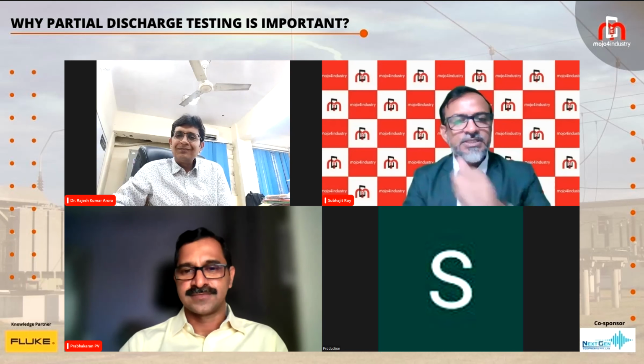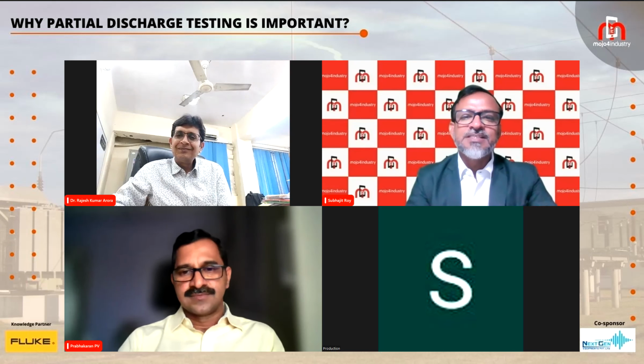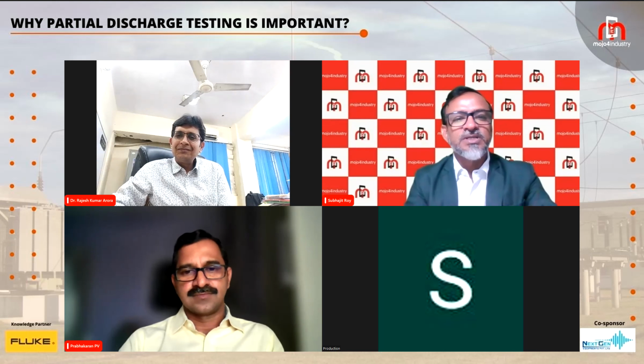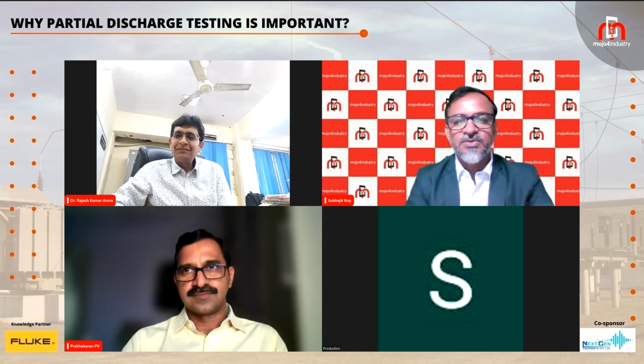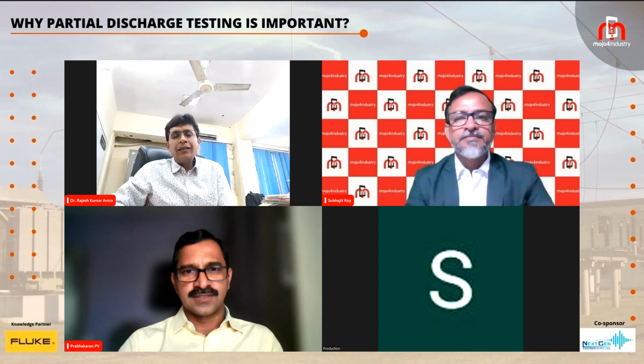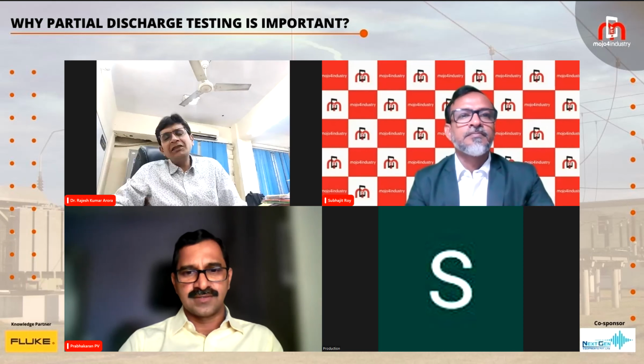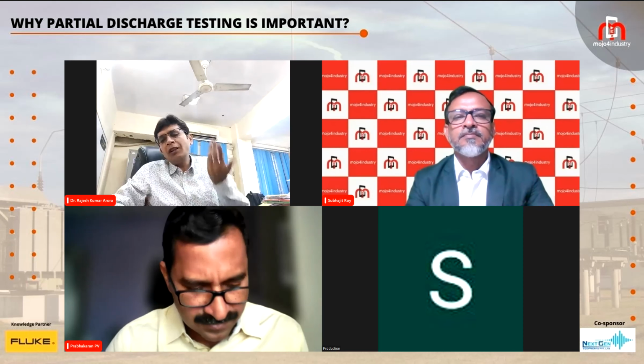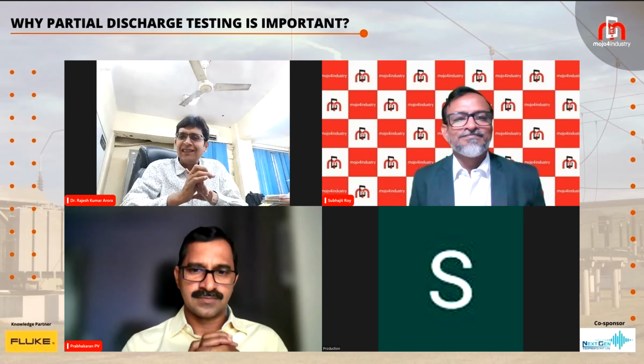One last question, from Sarat: are there any limitations for inception voltage and extinction voltage during PD? Dr. Arora: I don't think there's any specific voltage level as such. It all depends on the PRPD patterns we get, and based on that we identify the type of fault and type of PD in that equipment, and take corrective actions accordingly.